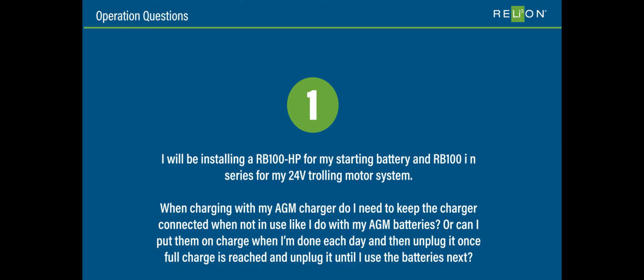Usually chargers have timeouts anyway, at 24 hours or something, where they stop charging the battery. If it happens to be float charging, it's not a tremendous setback to float charge the battery for a long period of time—you might lose 10 to 20% of the life. So there's a small preference, we would say unplug it, but most batteries shut themselves off, so there's no harm to unplugging it either. The battery's going to get charged, it gets charged, and it's done.